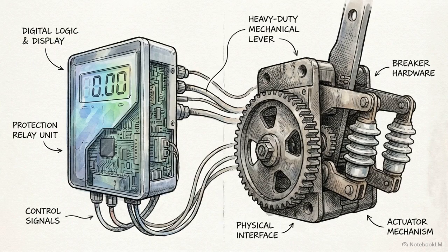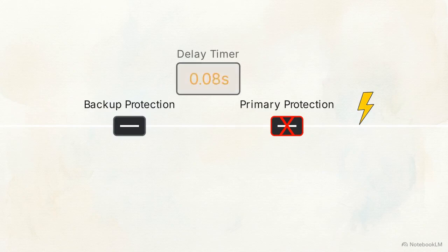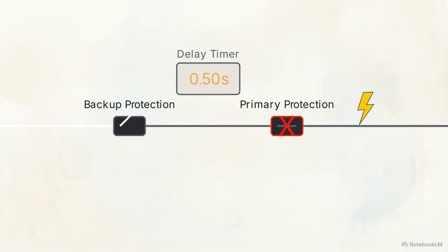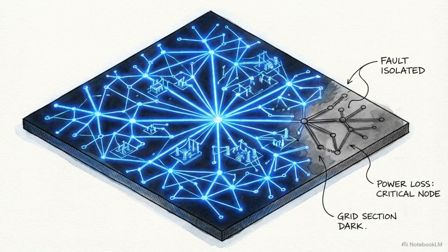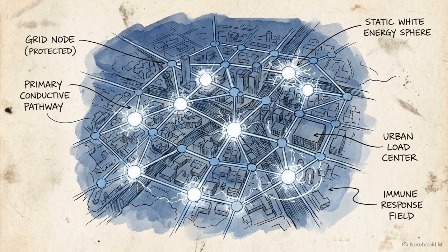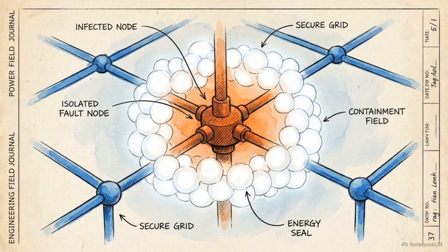The frontline combination we just witnessed, the lightning-fast math of the relay and the aggressive physical block by the breaker, is called primary protection. But engineers also build a second line of defense, called backup protection. If the primary breaker physically jams and fails to open, a backup system waits with a slight time delay, ready to step in and cut the power from further away. By layering these overlapping defenses, they ensure that a single broken switch doesn't cause a cascading failure across the whole grid. The power grid functions like a giant, highly automated immune system, constantly monitoring itself for infections and instantly isolating the sick parts to protect the healthy ones.